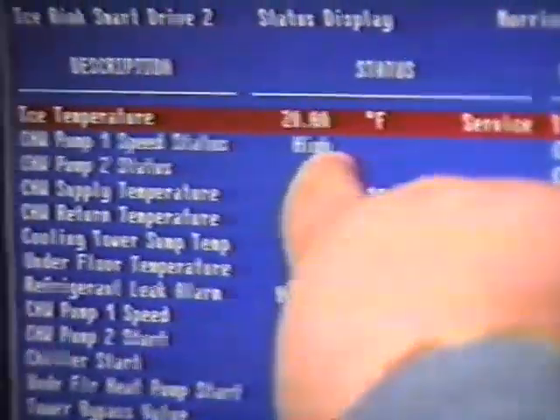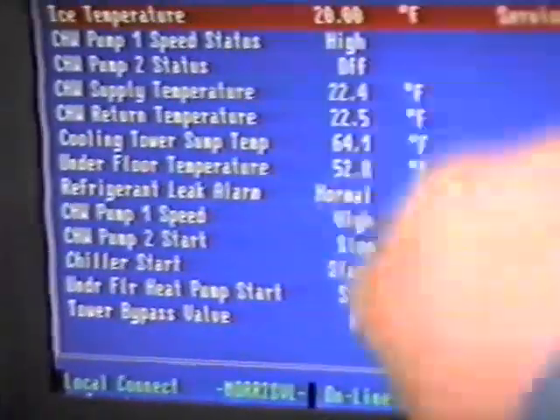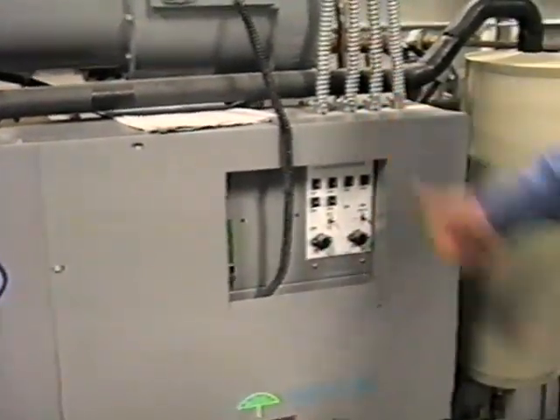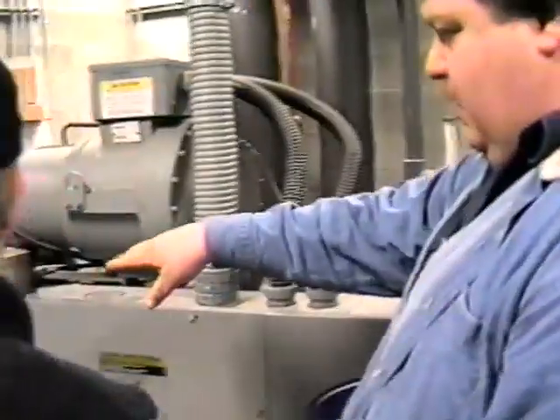Okay. So now I've got a high speed confirm. I set the high there. I'm telling it to go to high speed. This is the readback that it did do it. And then the chiller was started. And if we turn the switch on to remote contact, then this will do its timeout function, cycle up, and then we'll be able to see the sump temperatures change, the tower bypass valve. Might as well.